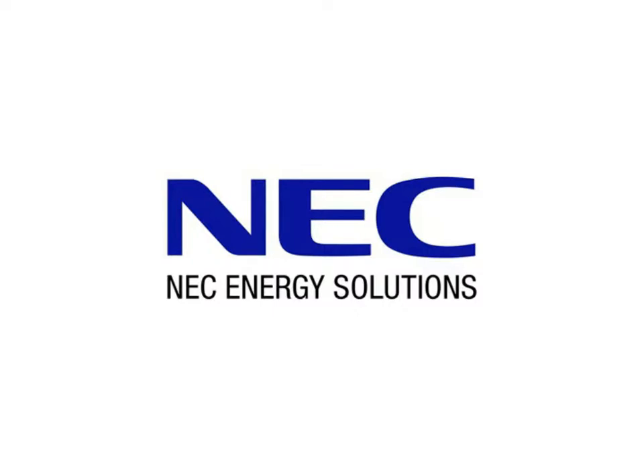Yes, they definitely are, and that's something we pay a lot of attention to because, in the simplest sense, you can always just charge and discharge very frequently and reduce the lifetime of the battery by really just going through too many duty cycles. Whereas if you take a more intelligent approach, you can still get these performance scores in PJM, but have less wear and tear on the battery by ramping up a little slower and ramping down accordingly and still meeting the requirements. So one of the more subtle but very valuable advantages of the control algorithms is to extend the battery life.